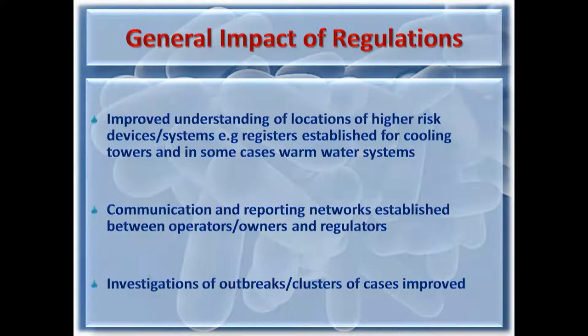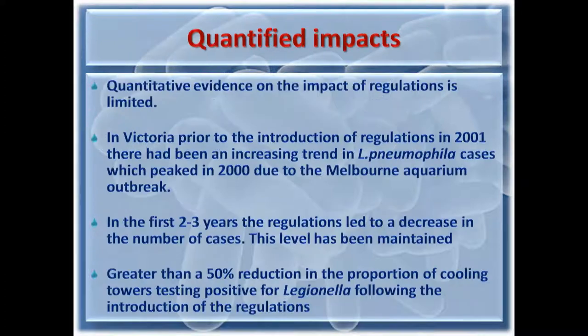Okay, the general impact of regulations. The good side is it's improved understanding of locations of high risk devices and systems. So we now have registers established for cooling towers, and in some cases we have registers for warm water systems. So the health regulators know where these systems are. We've improved communication and reporting networks between operators, owners, and regulators. And as a result of all this, our investigation of outbreaks and clusters of cases have improved. That's all fairly qualitative. We don't have quantitative evidence on the impact of regulations.